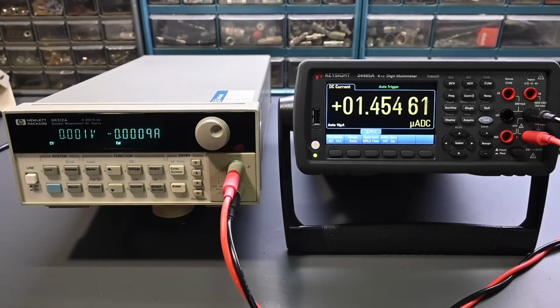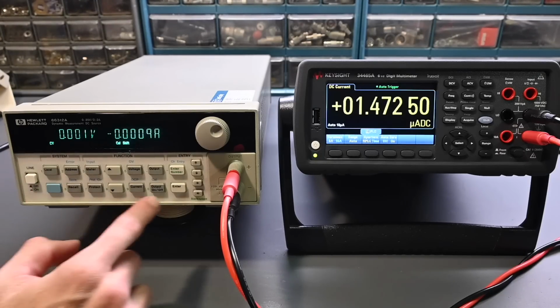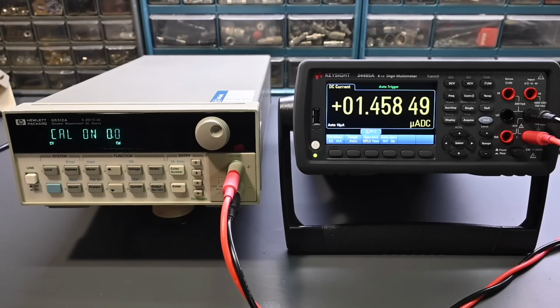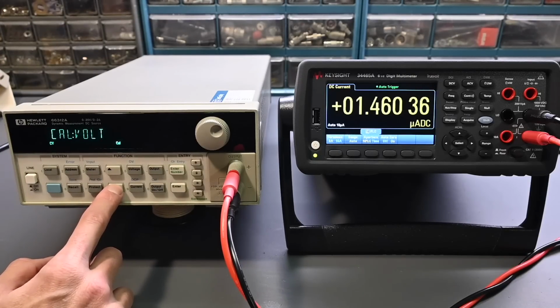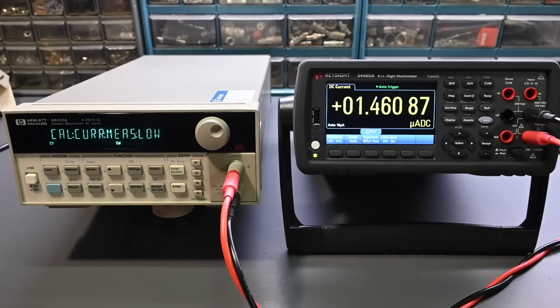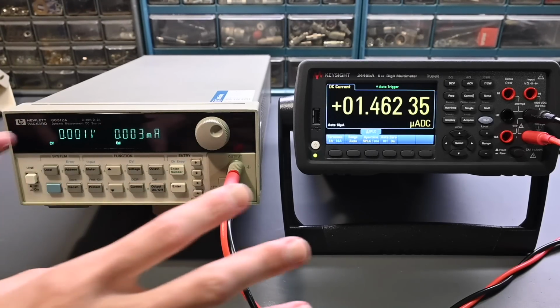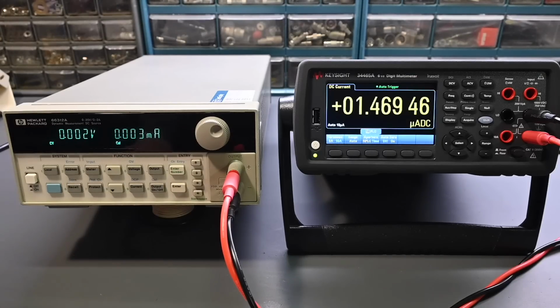Okay, now the low range current measurement. So I believe this is the point where we're going to need this other resistor. It says press Shift Cal. Cal current measure low. Right there. Press enter. It says connect the appropriate calibration load resistor as shown in figure B-1B, and then connect the digital multimeter in current mode in series with the load. Let me get things repositioned just a little bit here with this resistor. I need to use some different test leads to clip the resistor in place, and then we'll continue on.